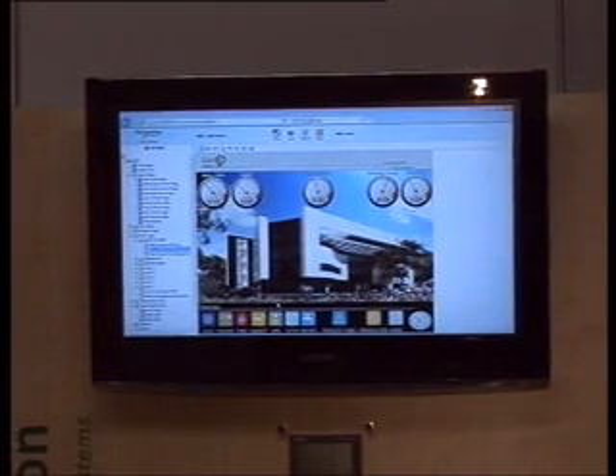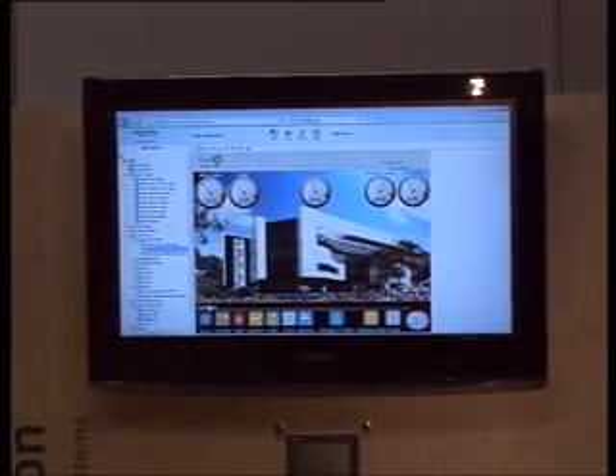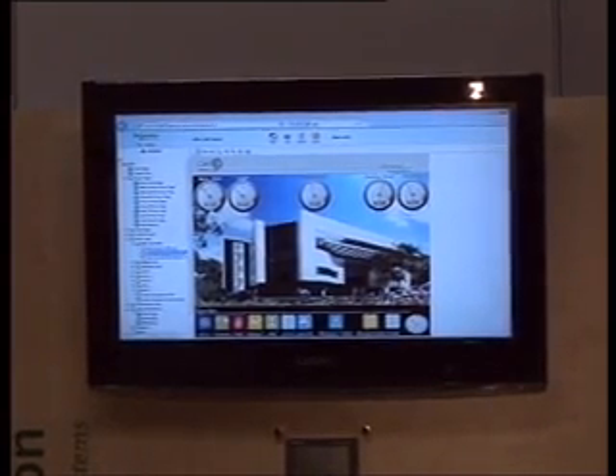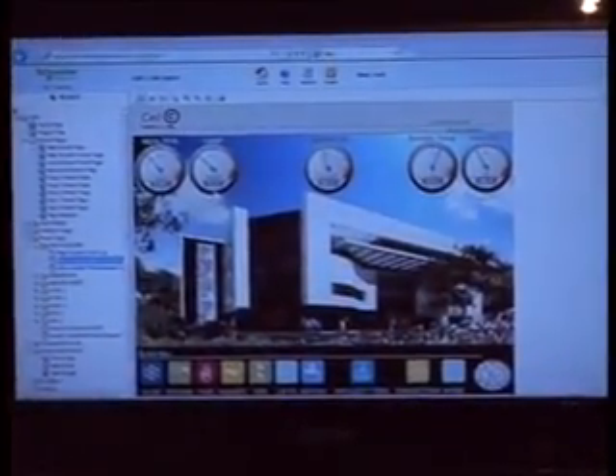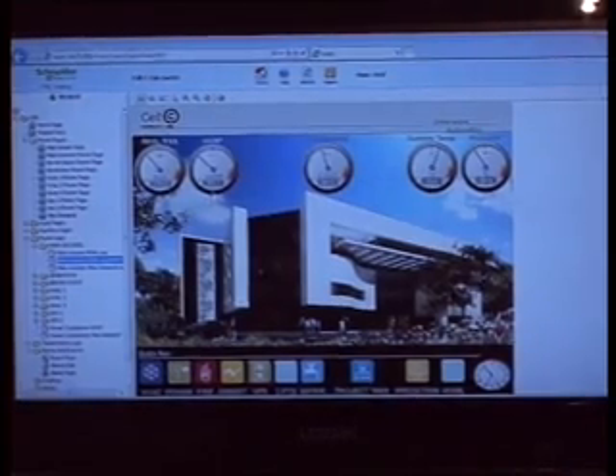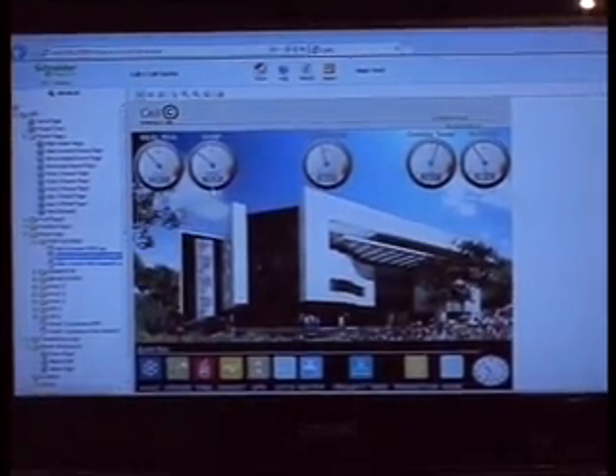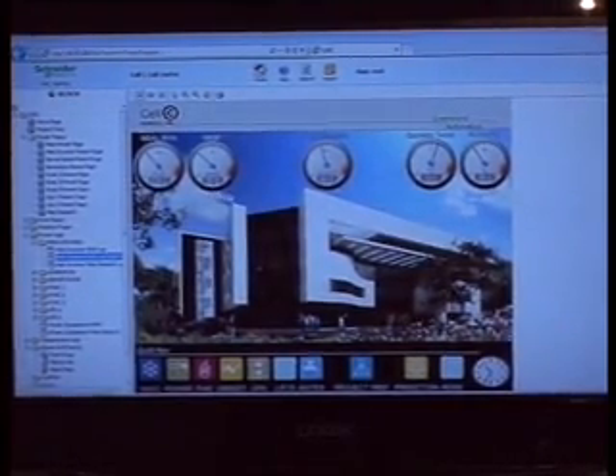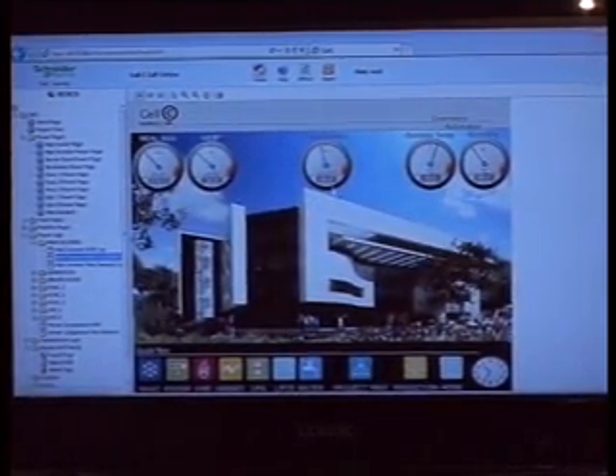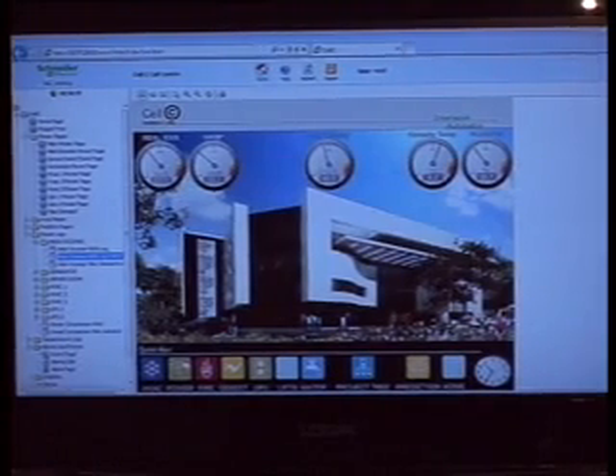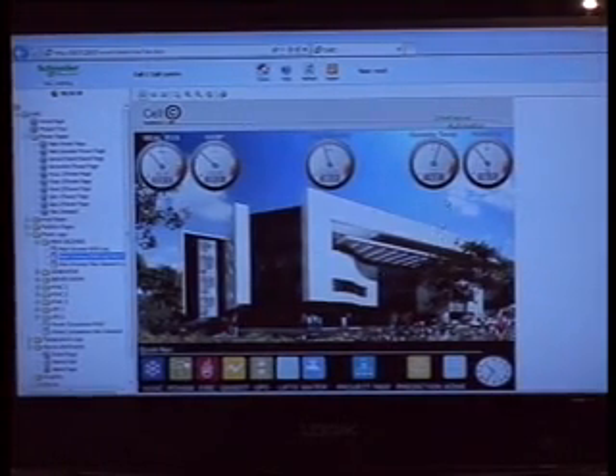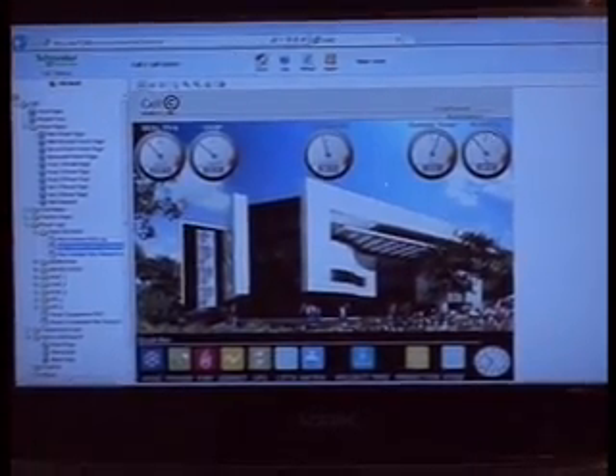Okay, we're logged on remotely to this building in Parktown. As we can see, we're integrating to the utilities of this building: HVAC, power, fire, generator, UPS, lifts and water. What we can see here is the live consumption of the building. So this value here is VA per square meter. This indicates how your building's performing against other buildings, so we can even drill down to a per square meter rate. Here we have CO2 in grams produced on the power that you're consuming at this present moment. And also we have outdoor ambient temperatures and humidity.